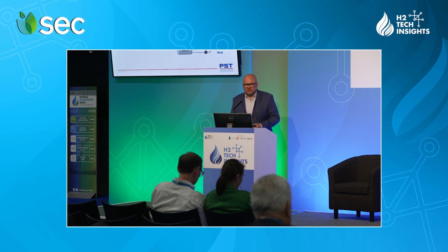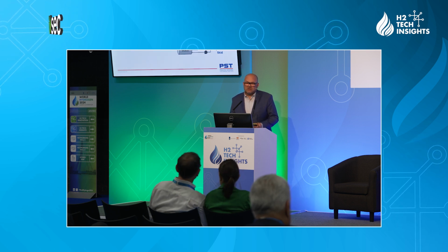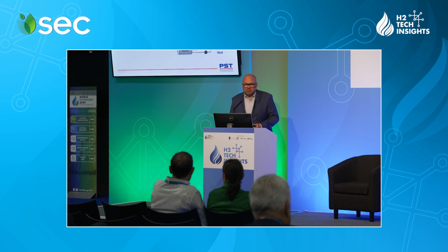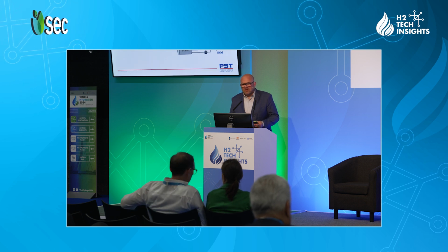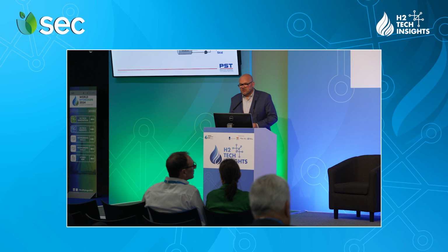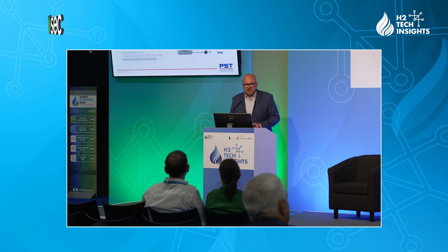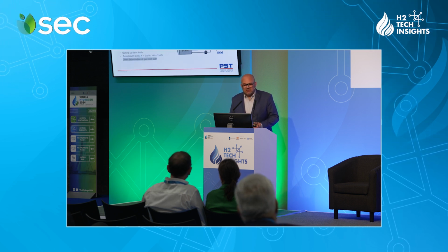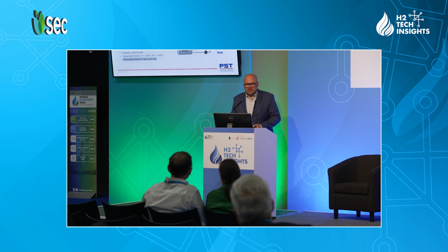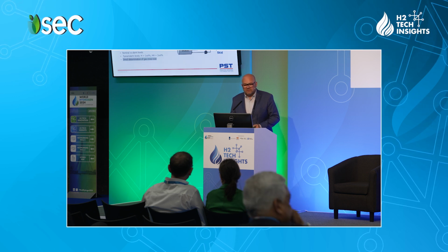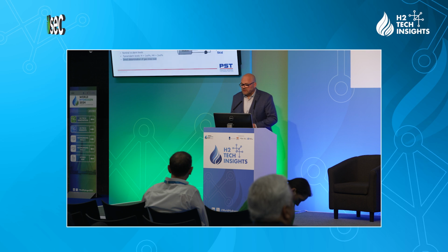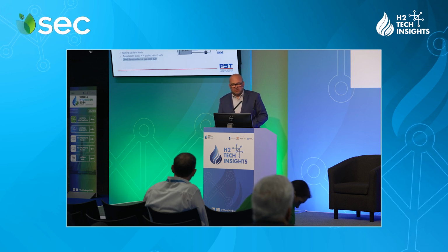Then there are nominal levels and alarm levels considered, of course, the typical alarm levels, typical I say, so some people do it slightly different. 1 volume percent is already a warning, and 2 volume percent could be something to switch off your system. And the same counts for the other side, hydrogen to oxygen. Same kind of levels are being used. And this could be, or is, a direct determination of the gas crossover.